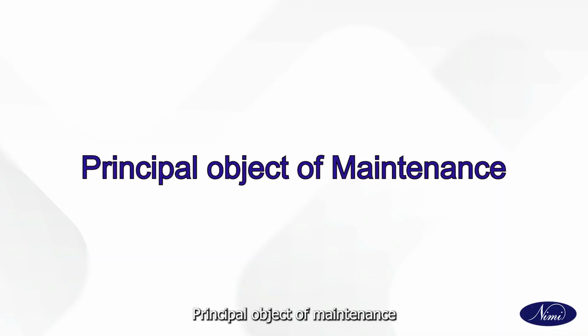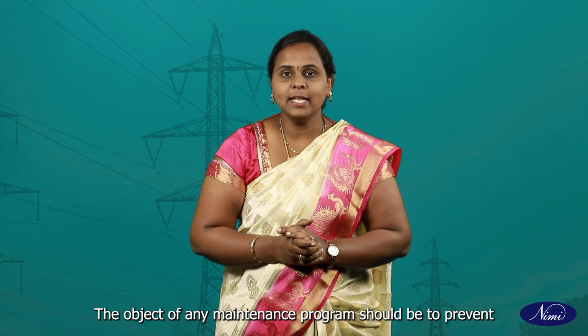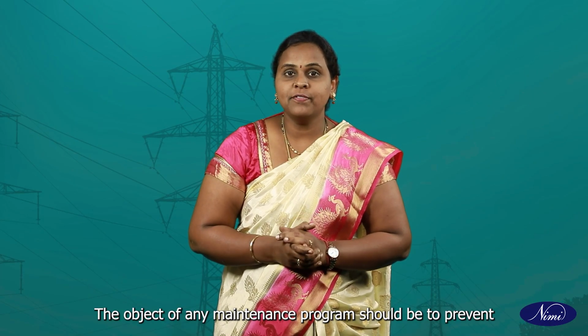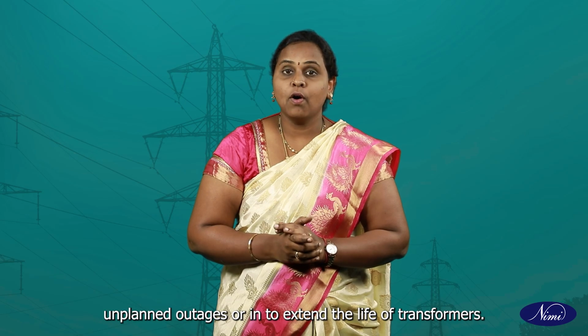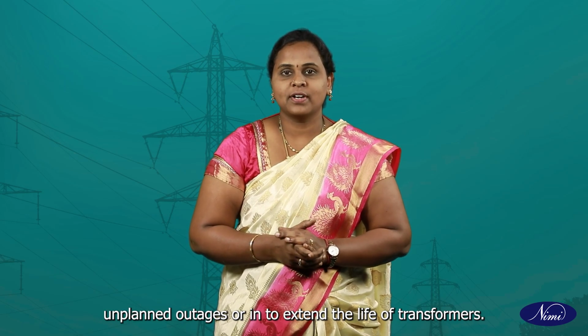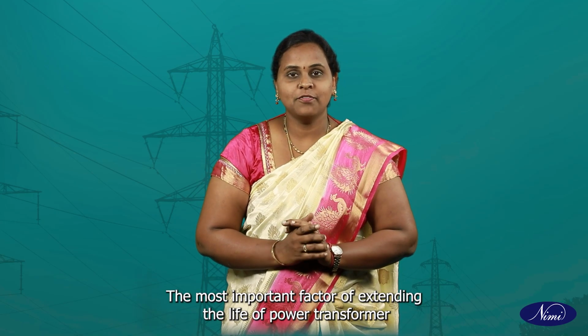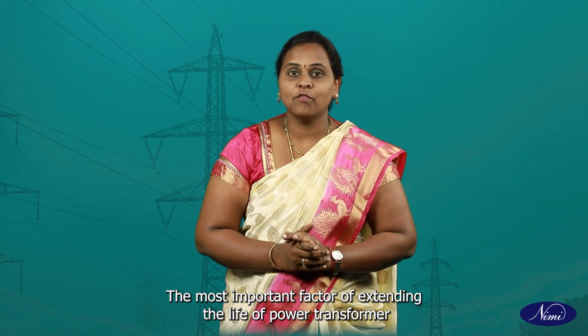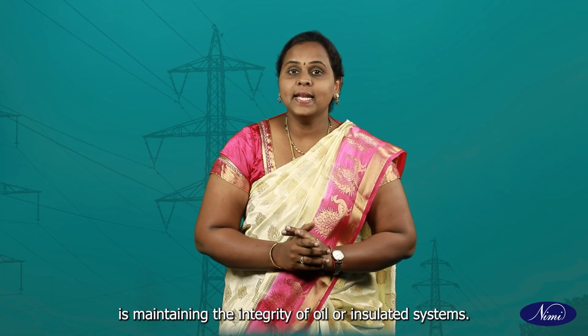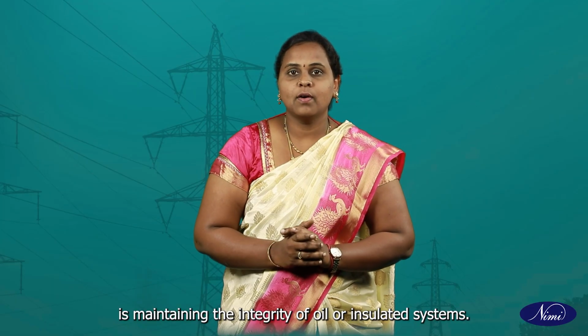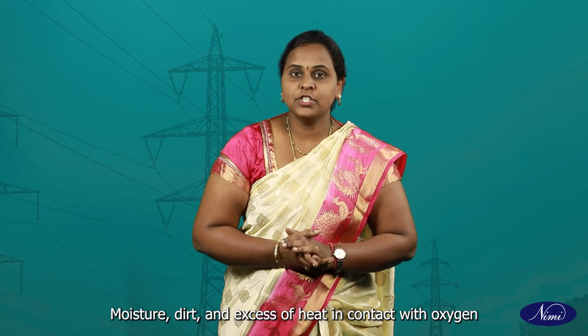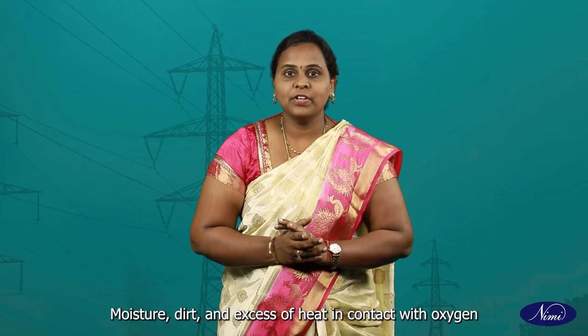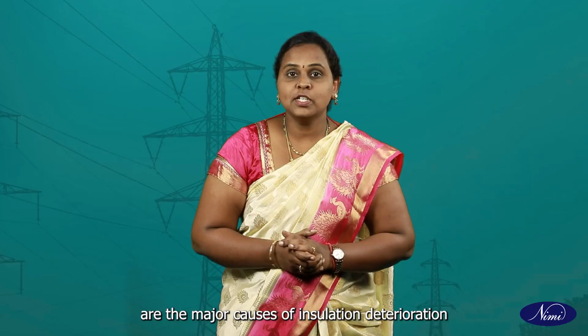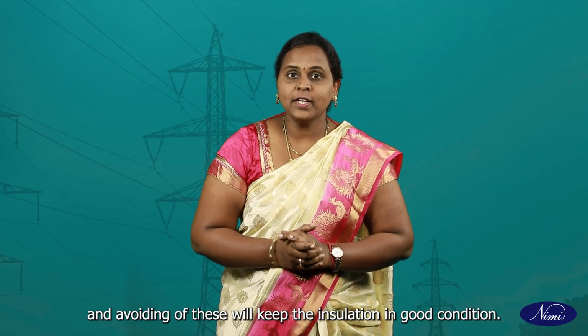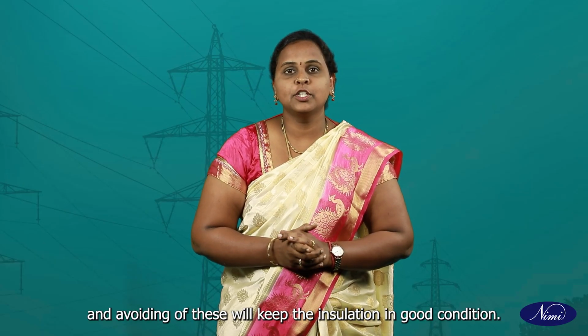Principal object of maintenance. The object of any maintenance program should be to prevent unplanned outages or to extend the life of transformers. The most important factor in extending the life of a power transformer is maintaining the integrity of the oil or insulated systems. Moisture, dirt and excess heat in contact with oxygen are the major causes of insulation deterioration, and avoiding these will keep the insulation in good condition.